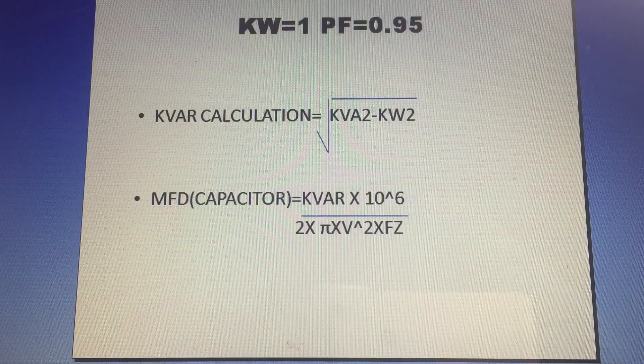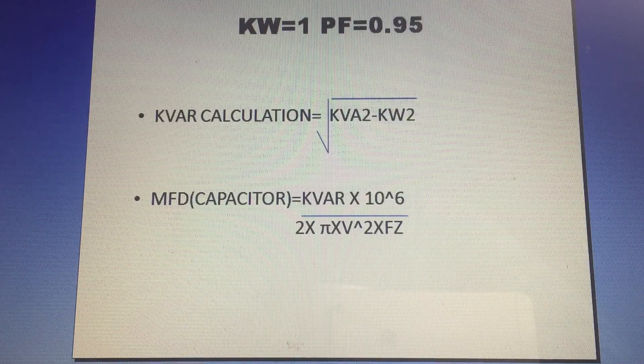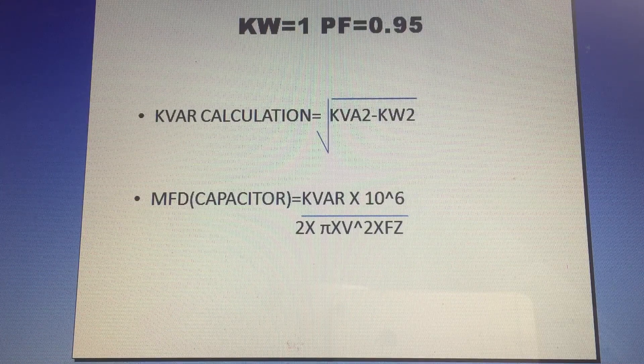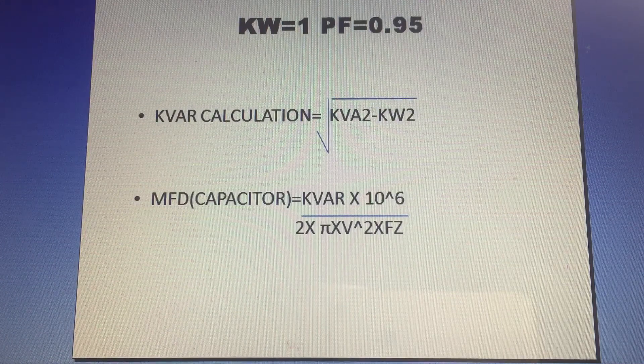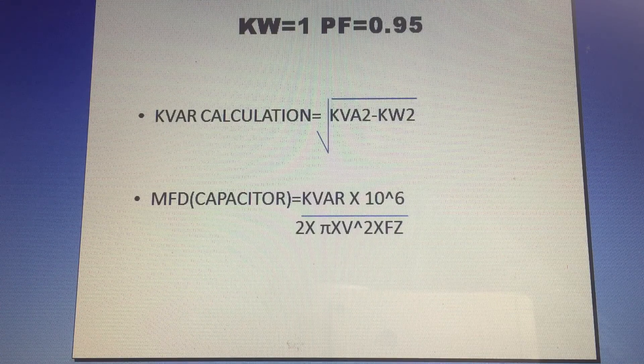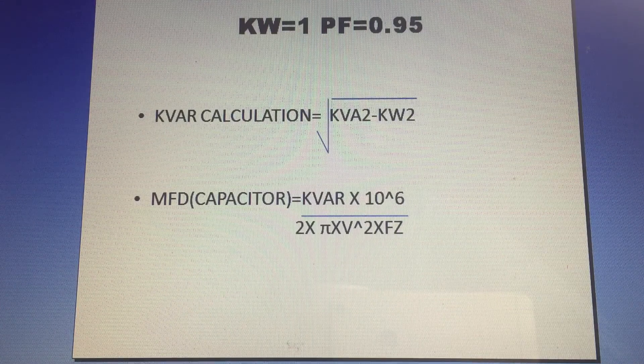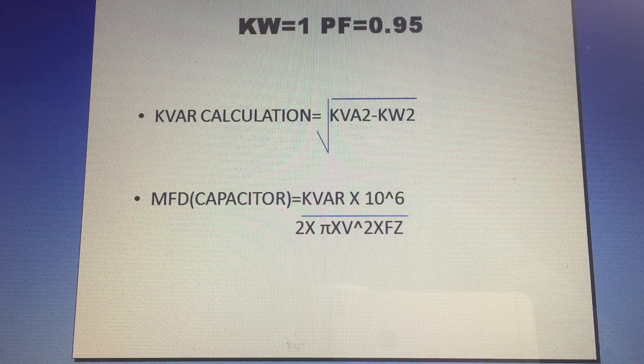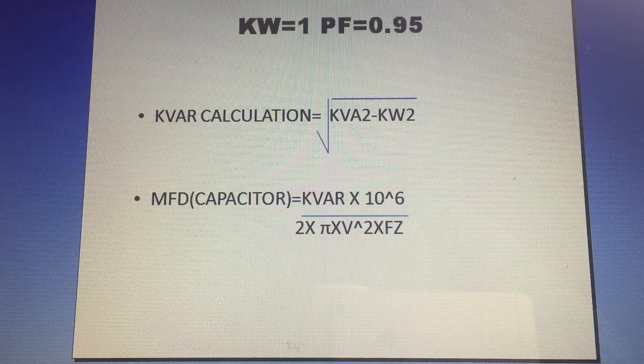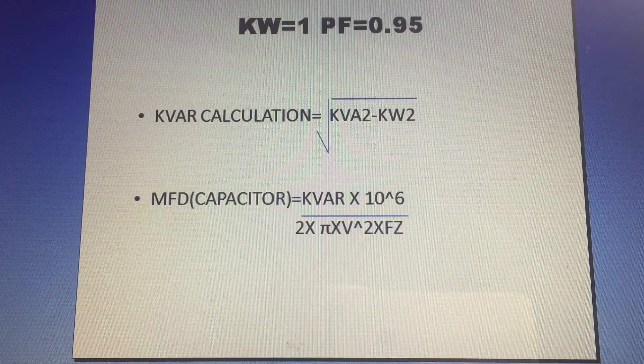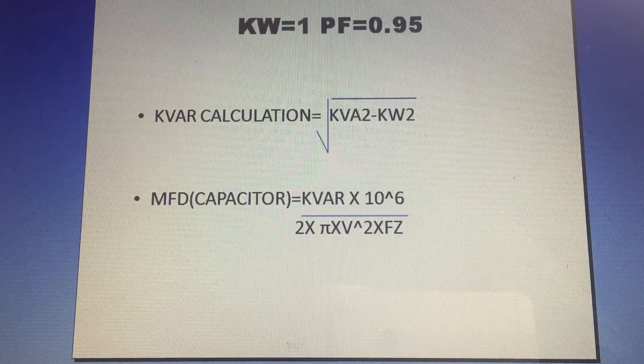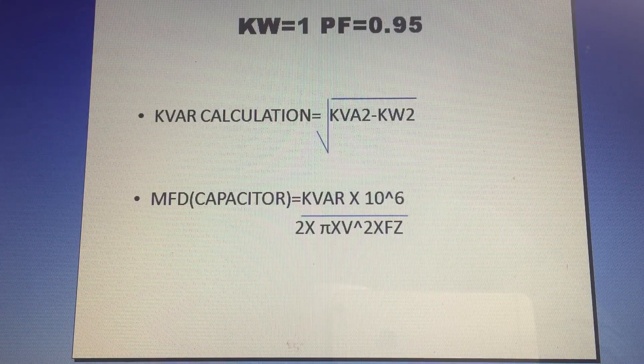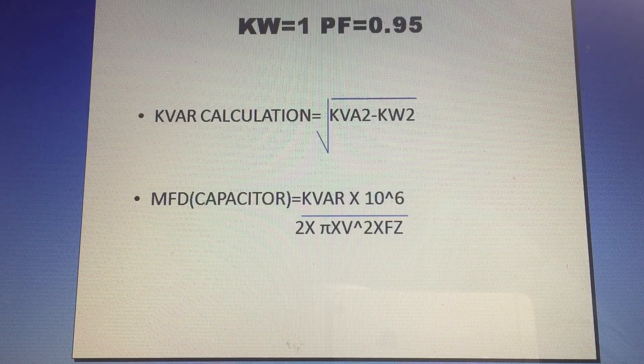The capacitor formula is MFD, that is the unit. MFD of capacitor equals kVAR times 10 to the power of 6, divided by 2 times pi times V squared times frequency. So 2 times pi is constant value 3.14, V is voltage 240 times 240, and frequency is 50 Hertz.